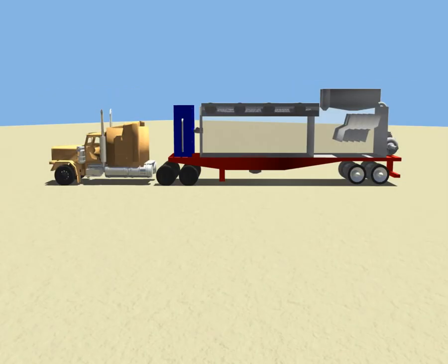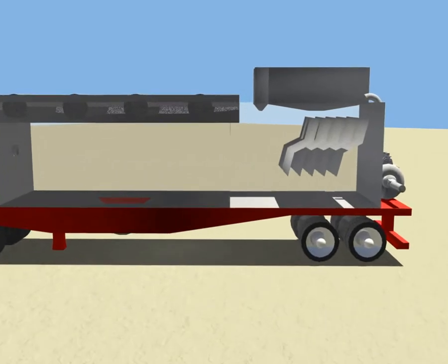The preconditioning process uses chemical additives to precipitate out of solution divalent cations such as calcium, iron, and magnesium, and heavy metals such as barium and lead. The process also removes large amounts of oils and greases. The stream is clarified so that a brine stream of mostly sodium and chloride ions enters the mechanical vapor recompression units.